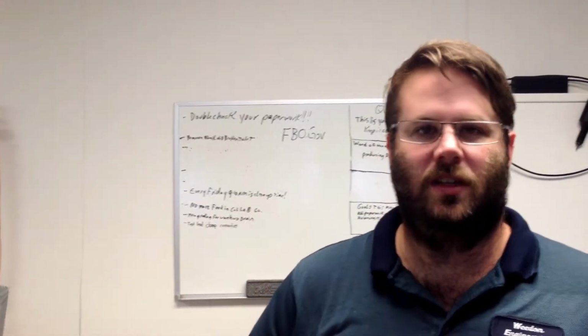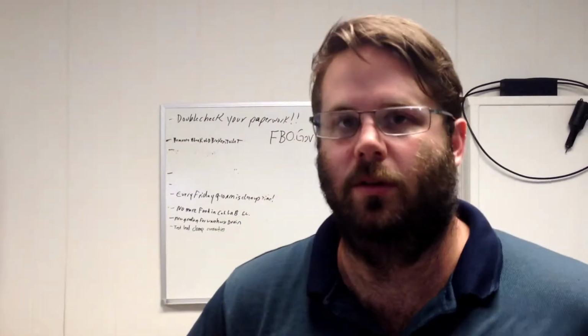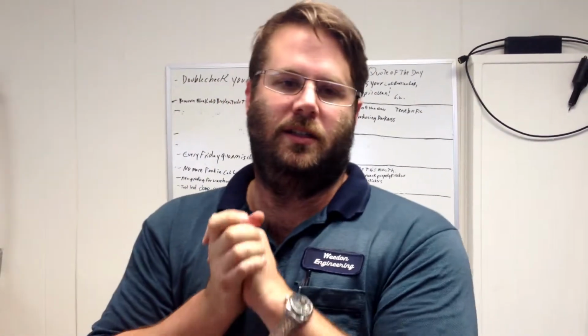I'm Greg. I want to make a quick video about calibration cycles and basically how often you should get your units calibrated, whether it's a torque wrench, micrometer, gauge, whatever, multimeter. The first thing is the default is normally 1 year, at least for our cal lab. That's the general default for everybody as well.